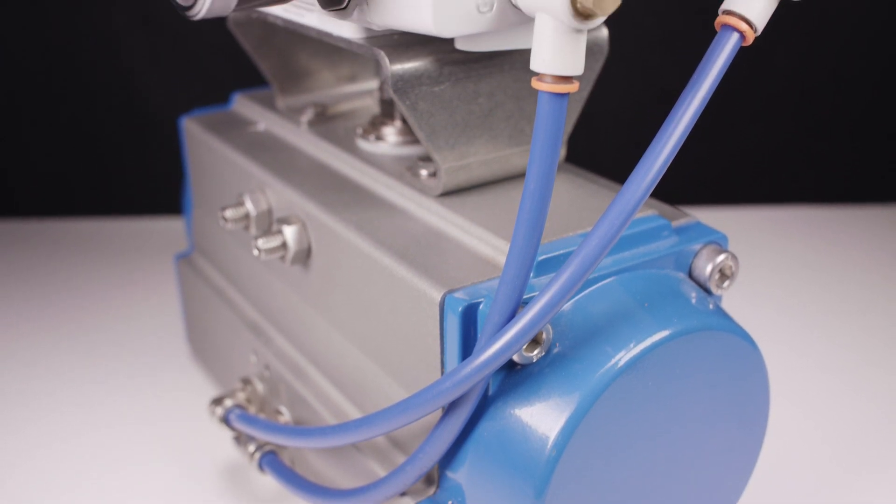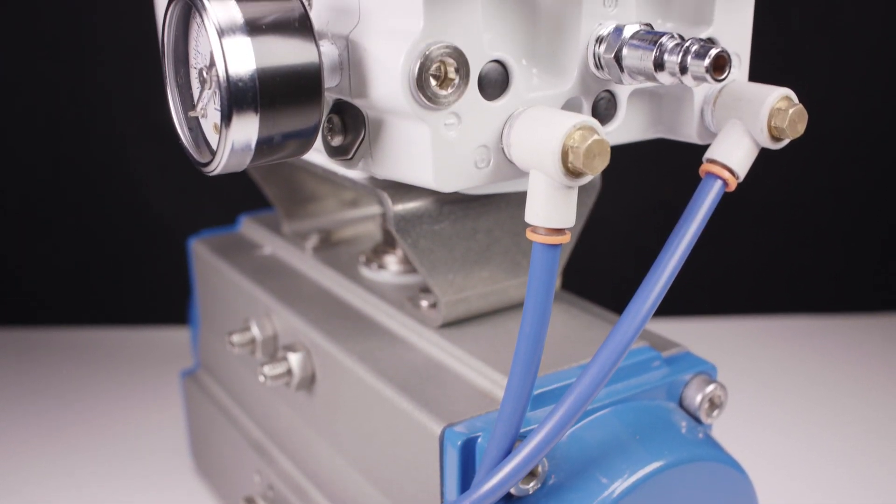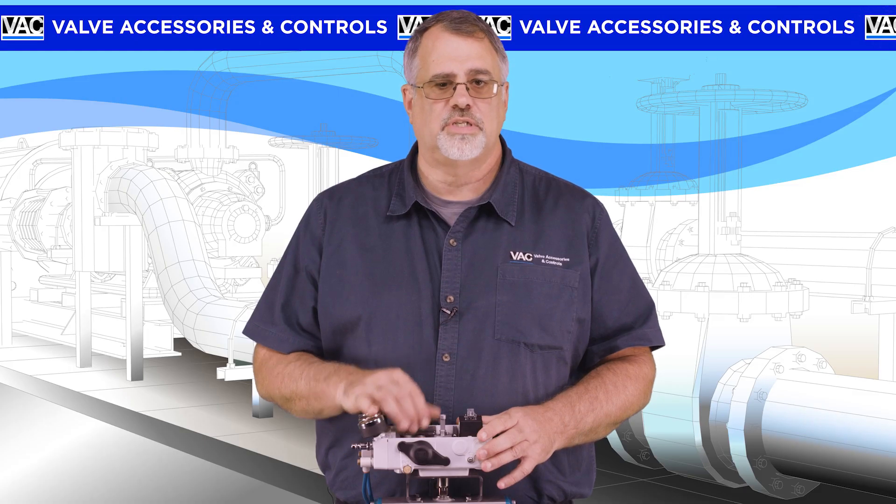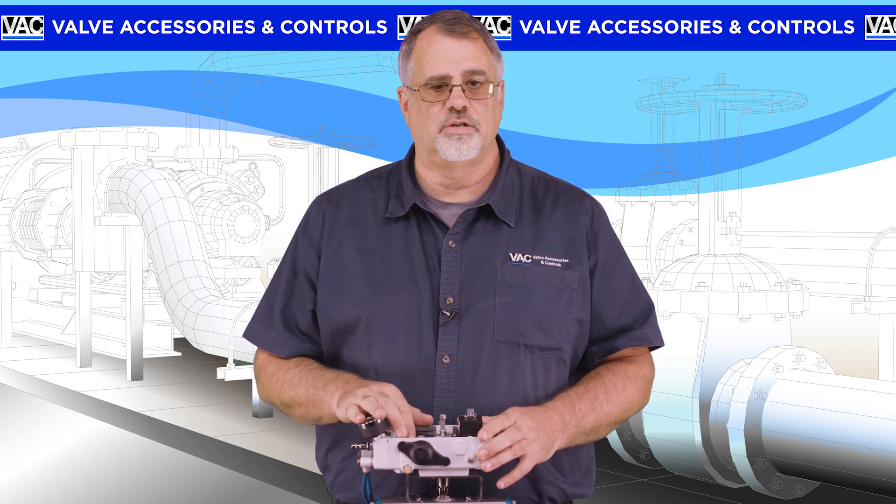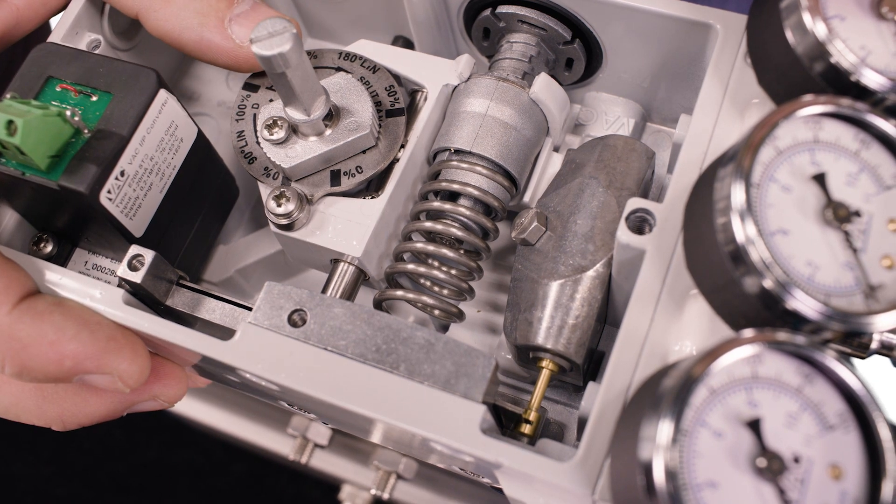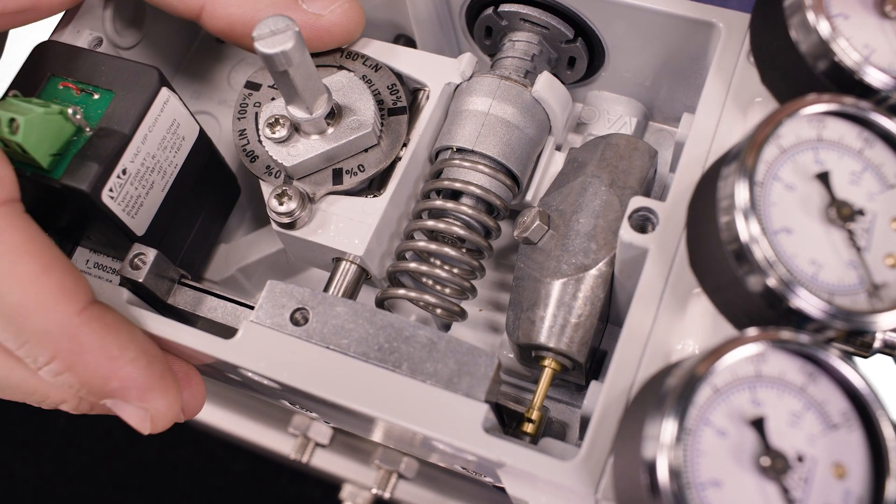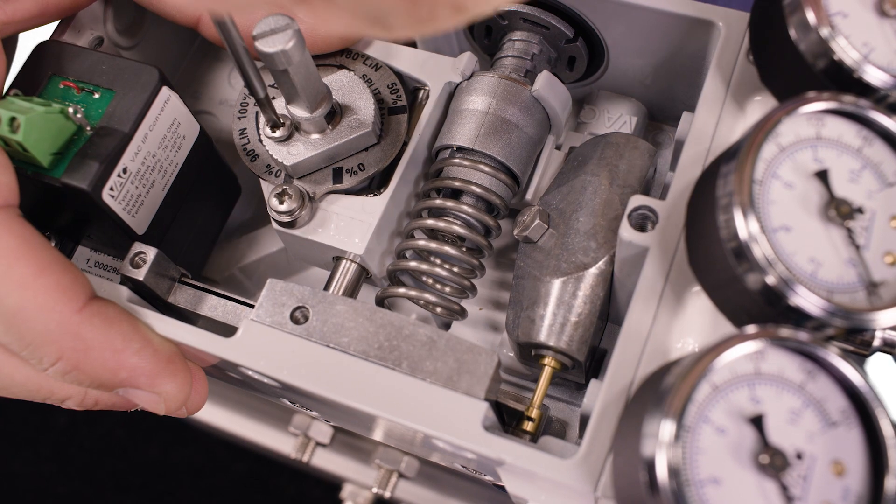With the positioner mounted and tubed to the actuator, and the actuator in the minimum signal position, the first step is to set the cam. Make sure that there is no air applied to the positioner at this point. Loosen the cam nut locking screw about two turns, and then loosen the cam nut just enough to let the cam move.